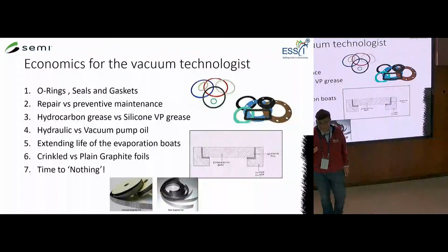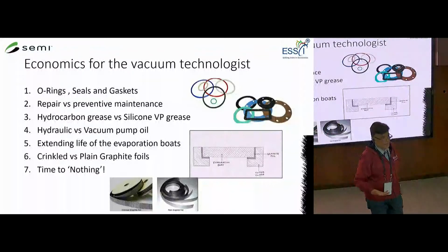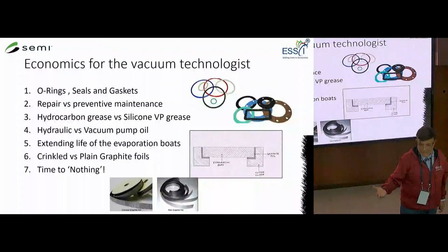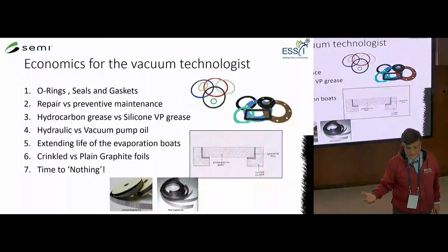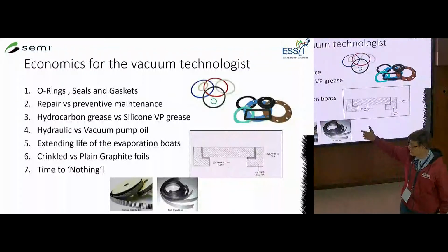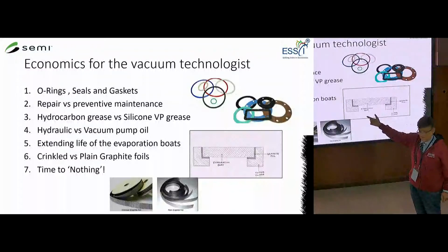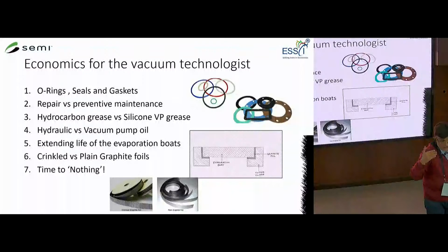Well, let me tell you, there have been instances when people thought that they could use the normal hydrocarbon grease in their vacuum pumps for semiconductors, and it can be a disaster. Simply because the hydrocarbon grease is based on hydrocarbons from mineral oils. They can degas. They can reduce the life of your O-rings and seals. For saving that little price, you will pay a very heavy cost.